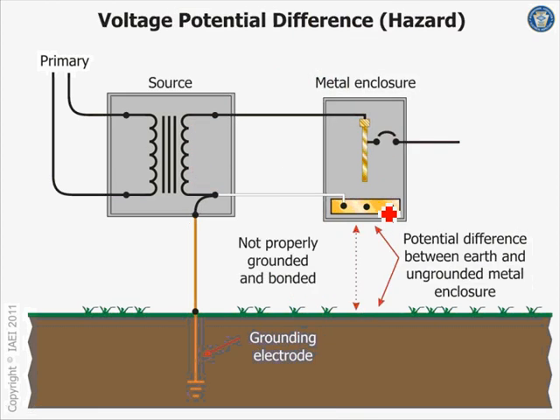Okay, now this is what they use in Europe and the Middle East. So you have a grounded system, exactly the same system, a grounded system, I'm not kidding you. So the voltage, and this is not acceptable here. My voltage coming here is 220. We don't use this system. Do we use 120 only, Jeff? I've never seen 120 only as a service. Maybe in the past we used it. But typically 220, 240, 120 is the smallest voltage that we bring to a building.